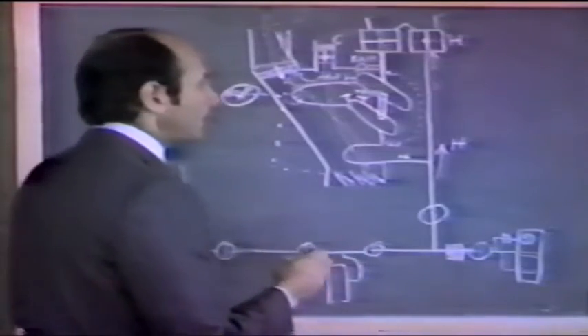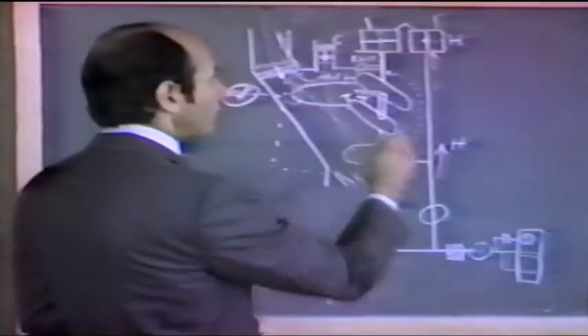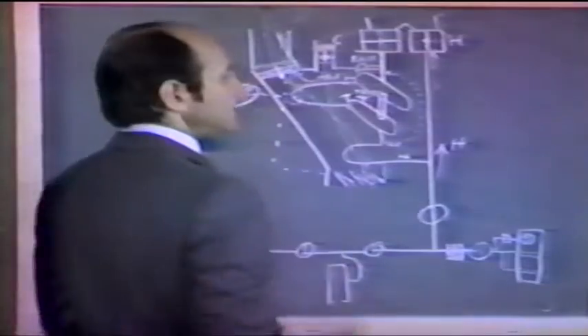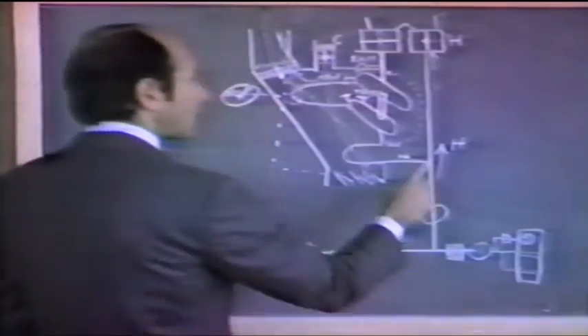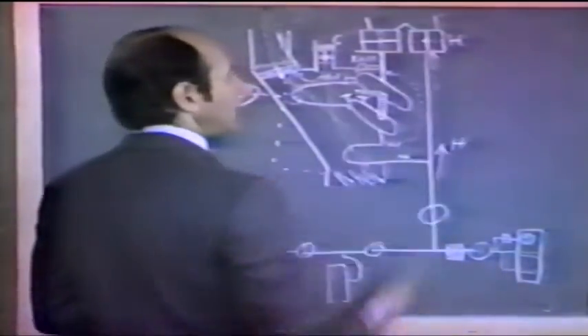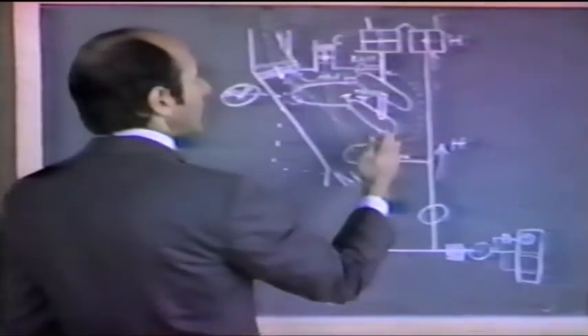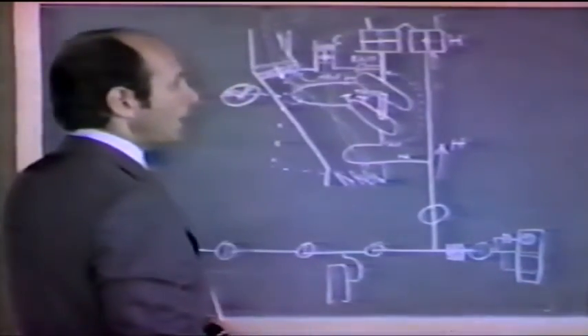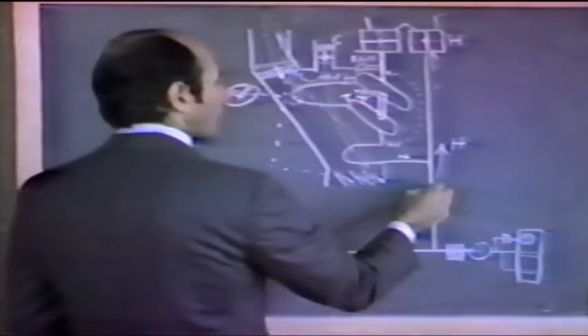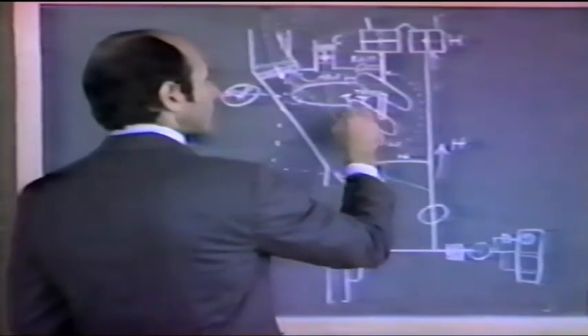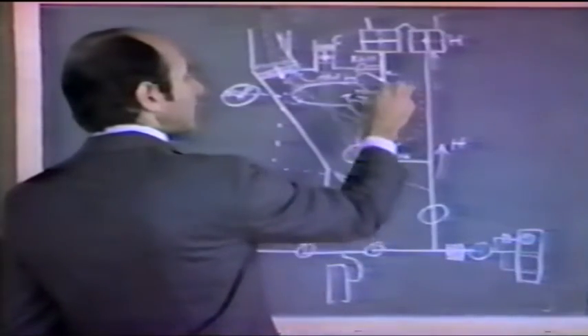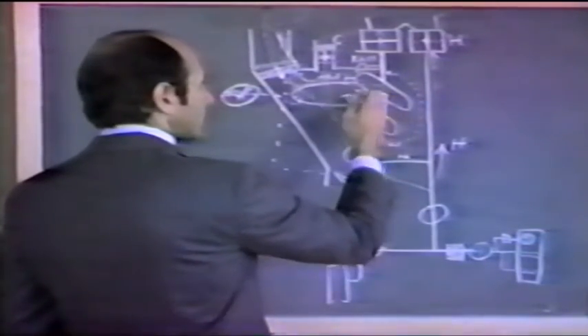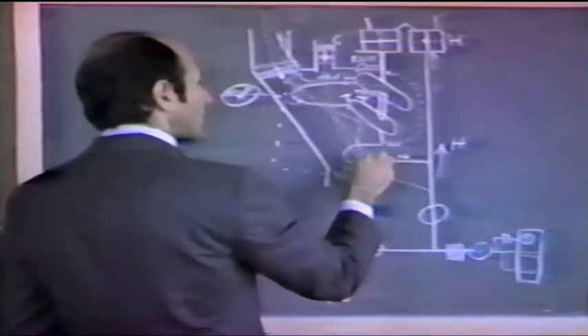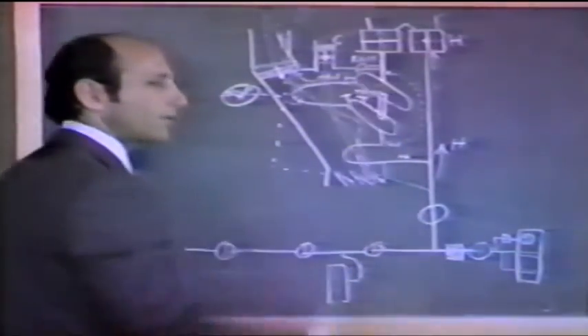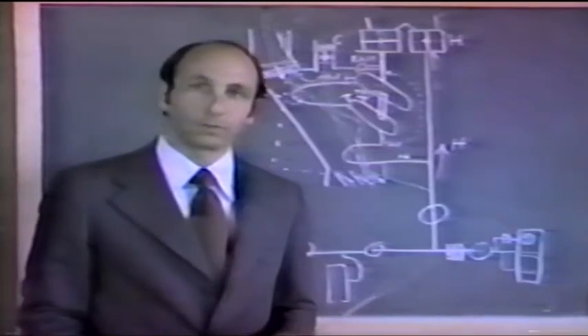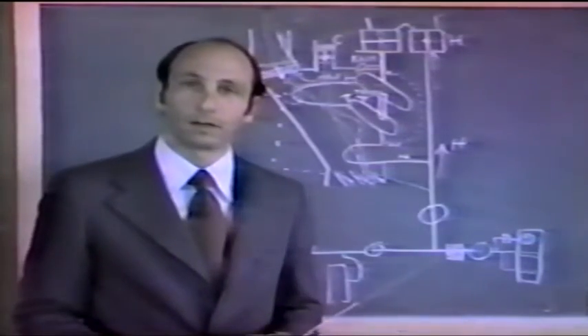On the advanced airplane, we have 3 air mix valves instead of 2. We've got an air mix valve for nothing but hot air, just like here. We've got an air mix valve for nothing but cold air, just like here. And we've got another air mix valve for air that has gone through the heat exchangers only, not through the air cycle machine, that is the compressor and the turbine, but through the heat exchangers. So we have a 3rd air mix valve that we'll call lukewarm or cool air.